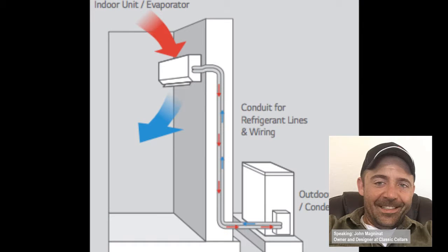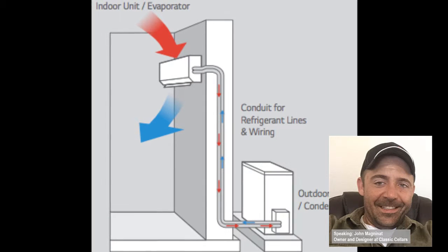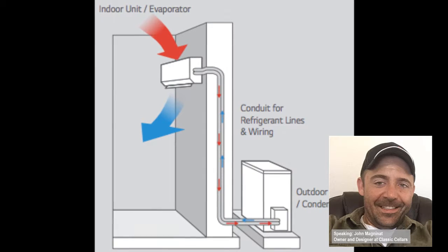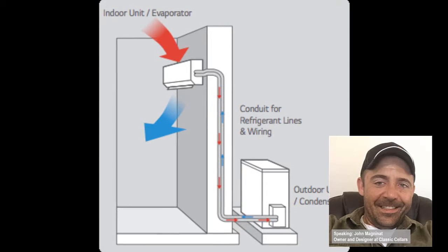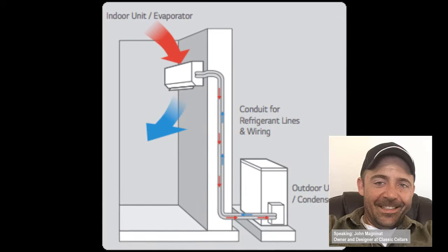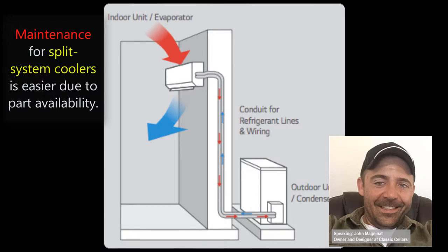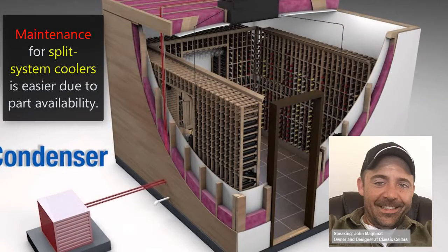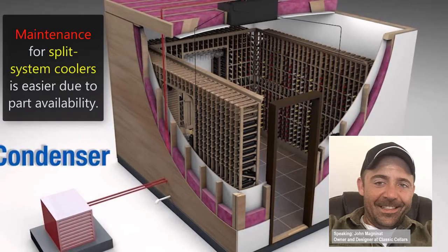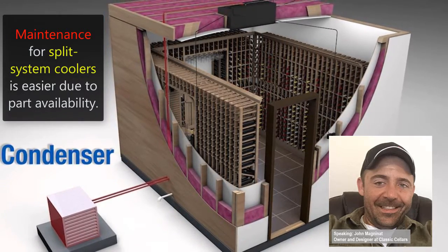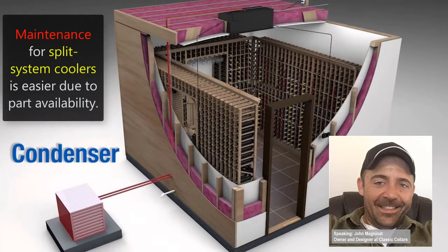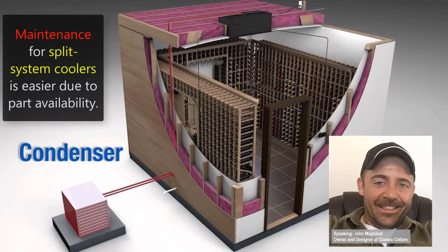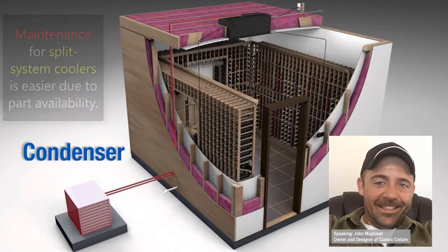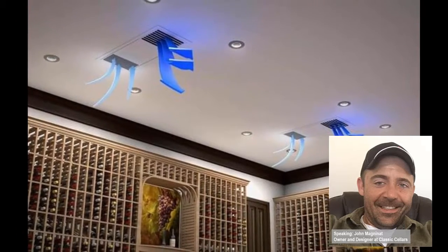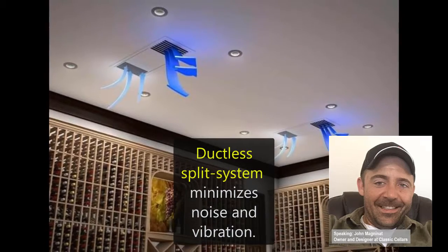I'm probably more of a fan of the split systems. The reason being, service-wise, the split systems usually run off of standard parts you can find at the refrigeration stores: little motors, controllers, stuff like that. So parts availability is probably a little easier for us on the split systems. With the split systems, you don't have to bring in your condenser air and your discharge air. You don't have to worry about all of that stuff. We can hide it with no ductwork inside the cooler, so you don't have any ductwork issues. There's a lot of benefits to that.